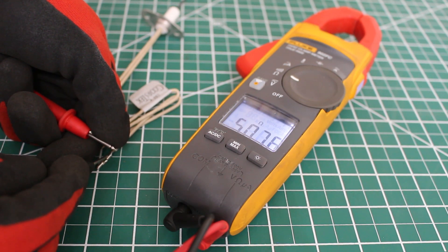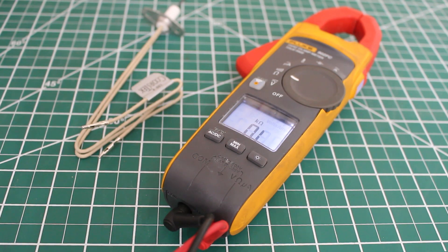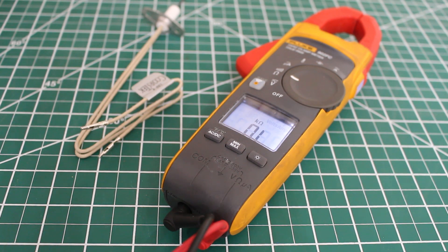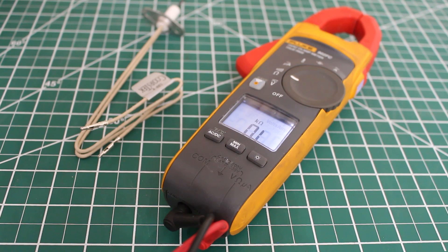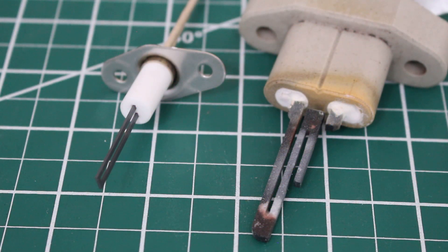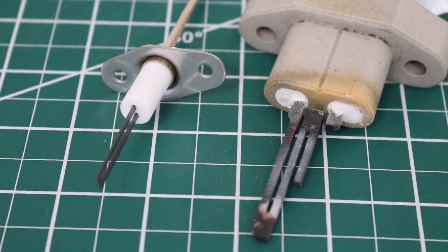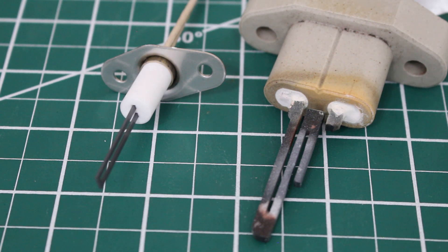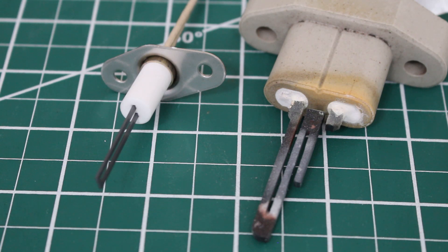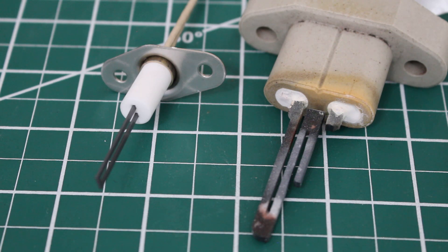As you can see we have 507 ohms. So that 40 to 90 ohm rule does not apply here even though this is a good hot surface igniter. Using resistance is not the best method as a different material or different voltage applied to that specific control will give you a different ohm reading. It's best to look up the specific model of hot surface igniter you have and see what the ohm reading should be.